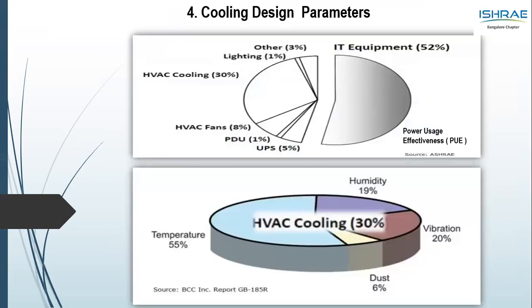So referring back to the PUE, the cooling I said 30%. If you break that 30% of the cooling down, the temperature within the data center accounts for 55%. The balance is the humidity, RH within the data center, vibration accounting for 20%, and dust 6%, because of the fact these are all closed loop, no fresh air is entering the data center, so not much worry on the dust. The major worry happens to be on the temperature and also on the humidity.